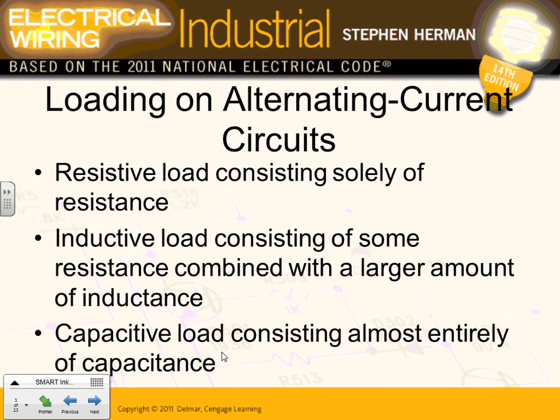Okay, most of the loads that we have, guys, a lot of loads are resistive loads, solely of resistance. The only load that's purely resistive is heaters. Boilers, heaters, anything that converts electricity into heat is a resistive load. Inductive loads, guys, like large motors, have an inductance in them. If you look at all the loads that we have in our project, I would say 75% of them are inductive loads. All the motors, right? All your motors are inductive loads. They do have a tiny little bit of resistance for the coil, but for the most part, it's a coil, inductive loads. And I'm not going to go back to the inductance and reactance and so forth.